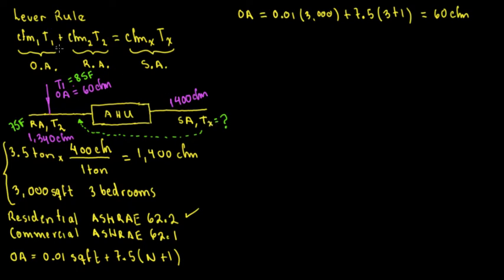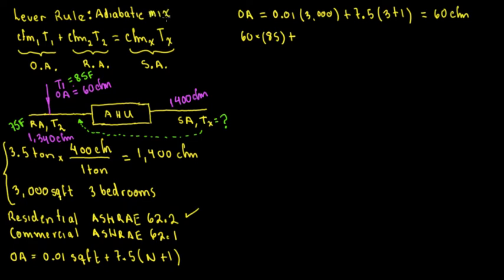Temperature X — we're going to put everything into the lever rule formula. CFM1 × T1 is 60 × 85. This is also called a weighted average, and in some books this lever rule is also called adiabatic mixing of two air streams — outside air and return air. CFM2 × T2 is 1,340 × 75, and that equals 1,400 × Tx.